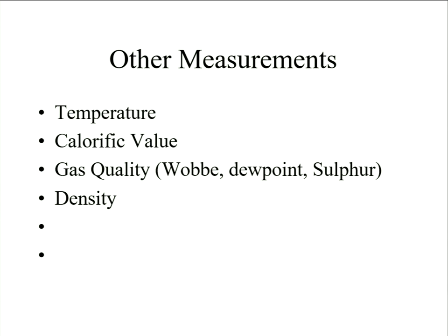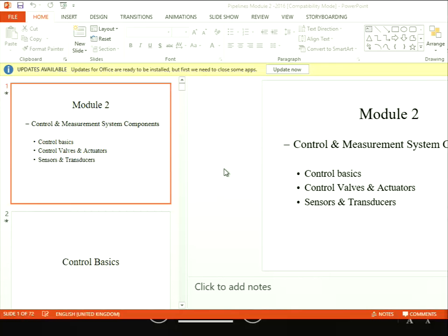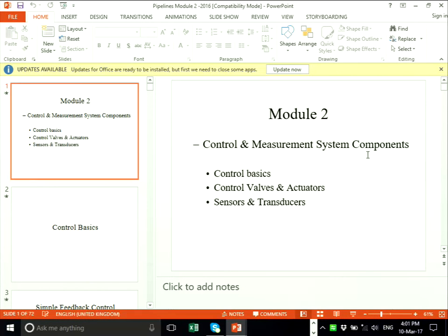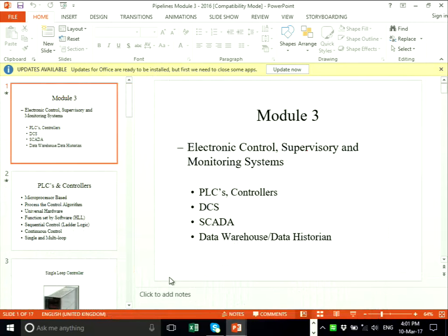So, your question about fiscal meters? Yeah, fiscal metering, the options. Well, generally you'll find that most of the contractual arrangements don't say use this meter or that meter. They'll say measure to this accuracy, and the standards will say what you've got to do, and people will test them using, in a lot of cases, Monte Carlo simulations to prove that they're accurate right across the range. But on the big sites now, you find ultrasonic is becoming more and more popular. It's stable over time. Orifice plates are still very popular, and the thing is, you can have spares.